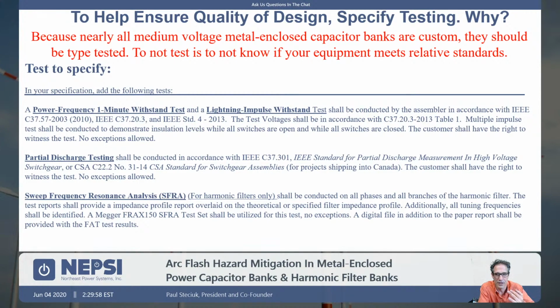You can easily design equipment to meet the withstand level. It's more difficult to design the equipment to meet lightning impulse withstand, and it's even more difficult to design equipment to meet partial discharge testing levels. So if you're looking to specify reliable equipment, specify these tests. It will help to guarantee that you purchased equipment that meets the standards and that has a high reliability and therefore a low likelihood of arc flash within the equipment itself.